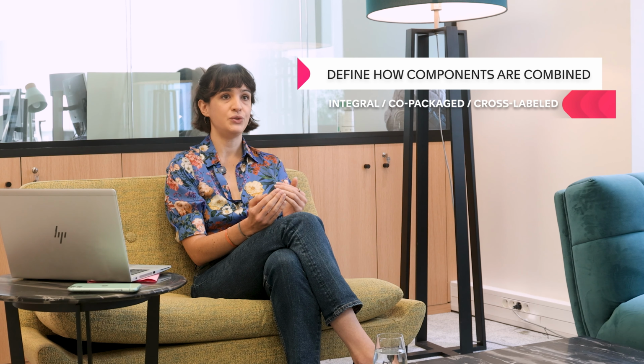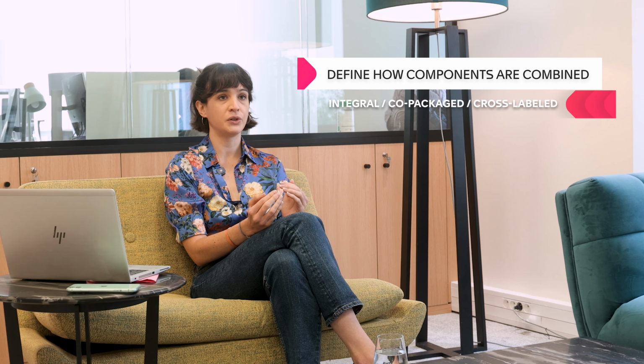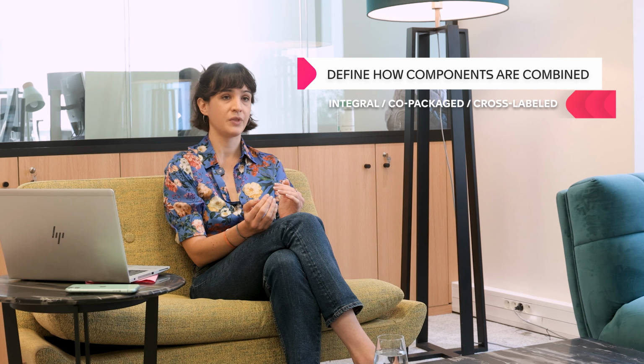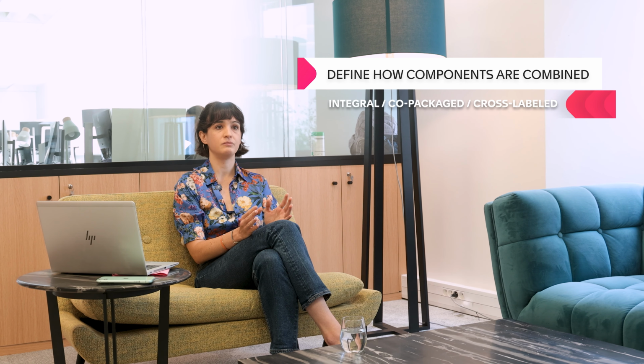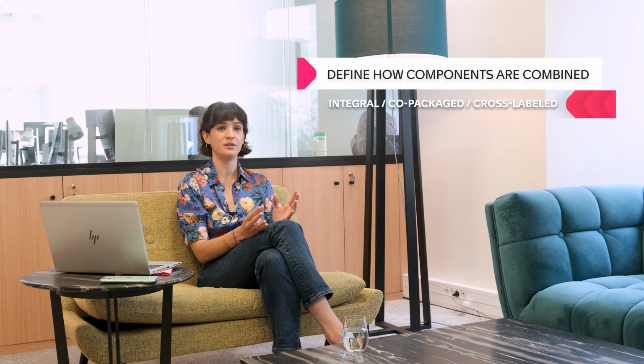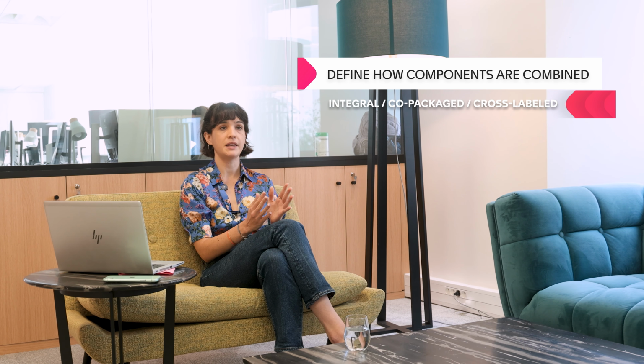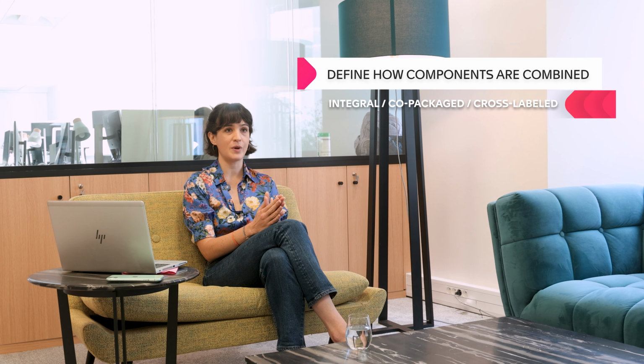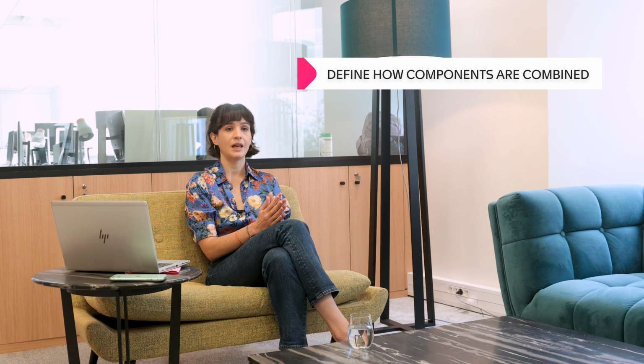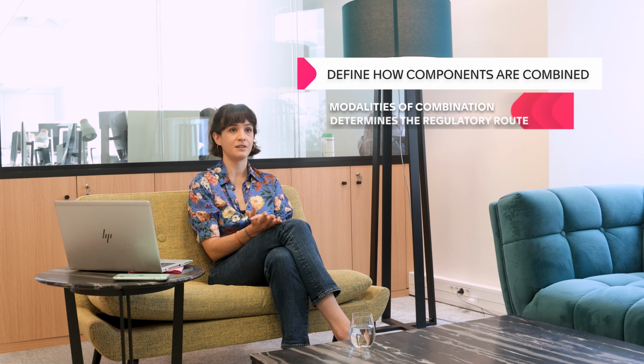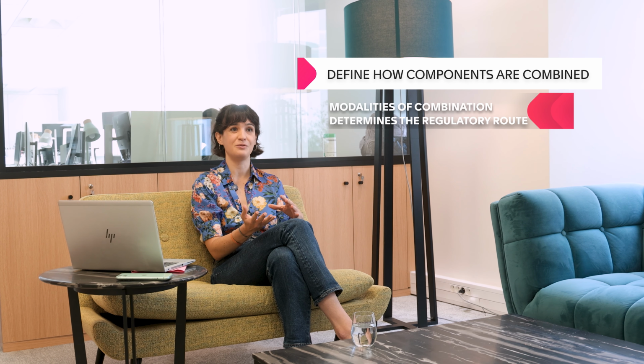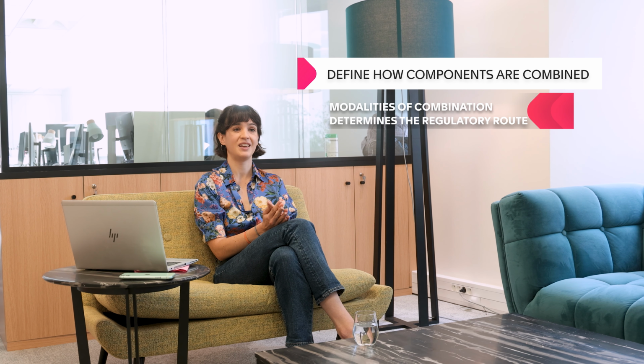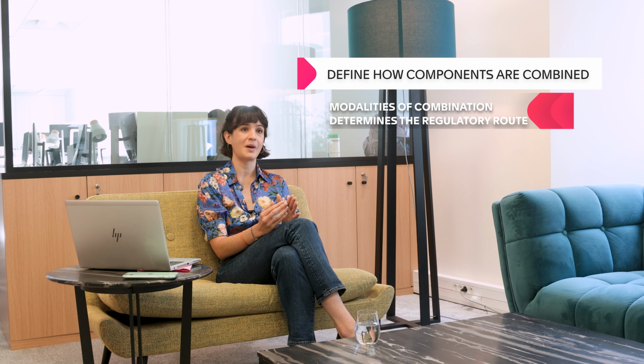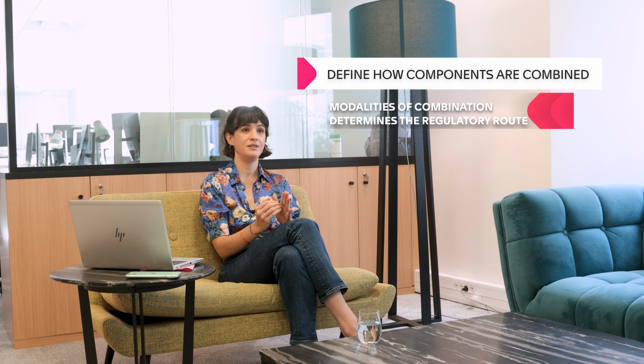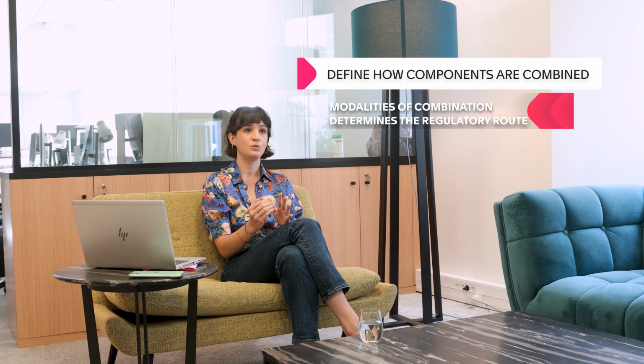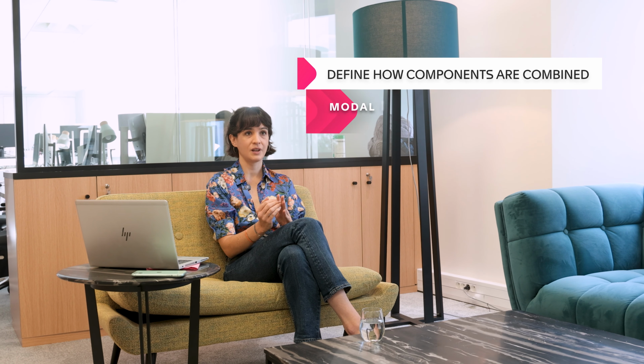The second question we need to be clear about is how the products are combined one with another. So we have the three styles of combination we can see with combination products, which are integral combinations, co-packaging, and cross-label. And depending on which scenario we are in, or multiple scenarios if we have more components than that, it will help understand and determine what regulatory assessment and route will be followed for each component.